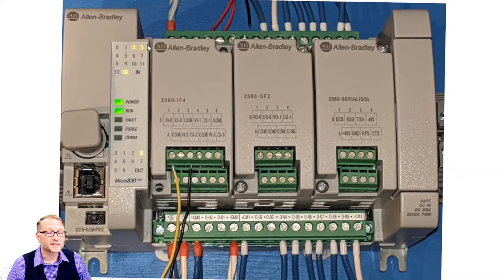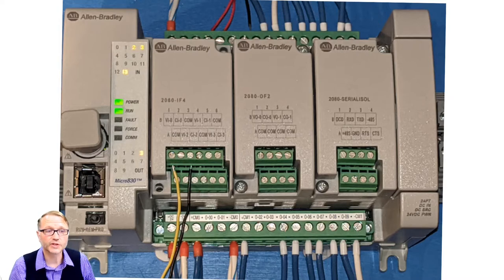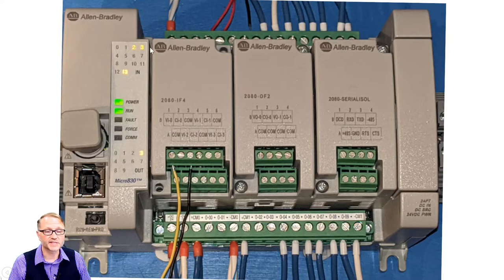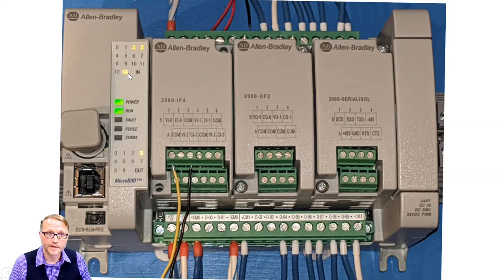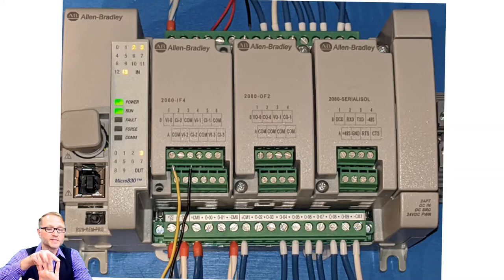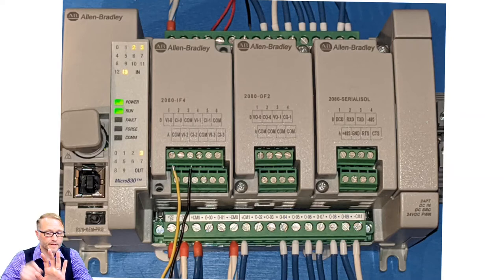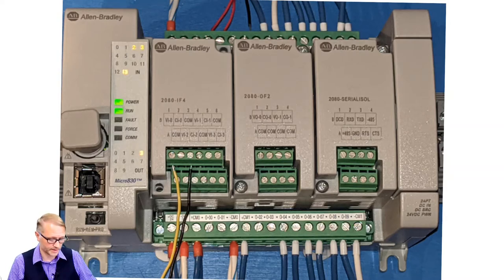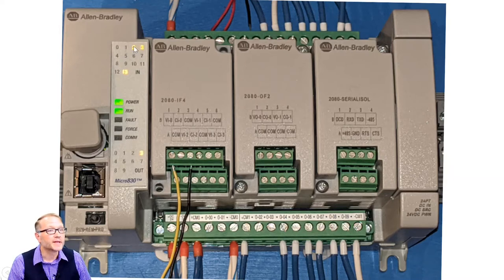A PLC has things you can look at. That's the theme of the lecture today, things you can look at. And what you can look at are the input status light emitting diodes, LEDs. In this particular case, you can see that input 2, 3, and 13 are active. This is input 0, 1, 2, and 3. So those are the red wires. And 13 is way over here. Now, how many inputs does this have? The answer is not 13. The answer is 14. You have to watch out for that. So if we have input 0, 1, 2, 3, and 4, and if you said that the answer was 4, that is what's called an off by 1 error. You have to guard against that. It's a pretty common thing in computer programming. It even has a name, OB1.